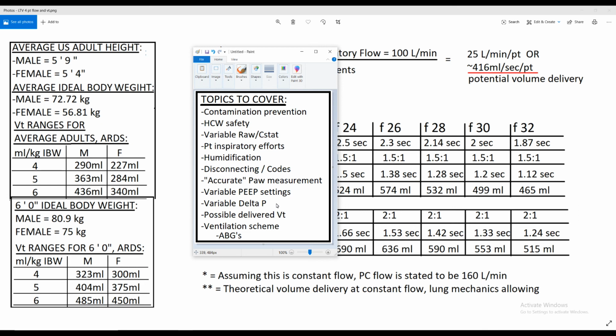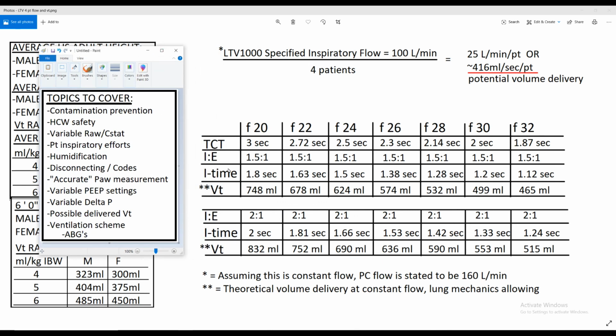You could also manipulate the driving pressure by changing the PEEP, but we know that we probably wouldn't want to be adjusting our PEEP too much, because that's going to have a huge impact on our tidal volume that's delivered. How much tidal volume can get delivered, this is what we were talking about down here. So again, just rough estimates of what this ventilator is theoretically capable of delivering on a 4-patient setup on a per patient basis, with just some pretty common settings that we might see.